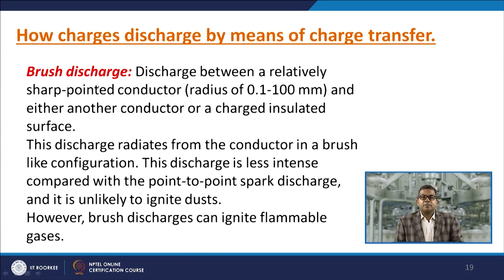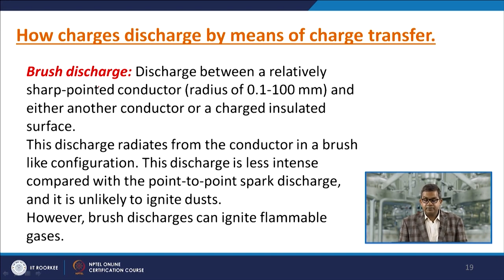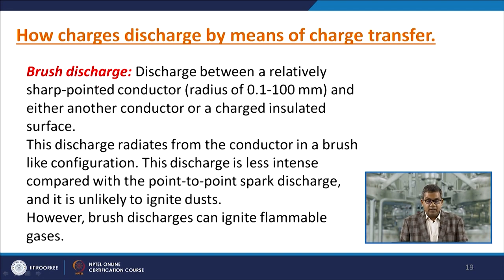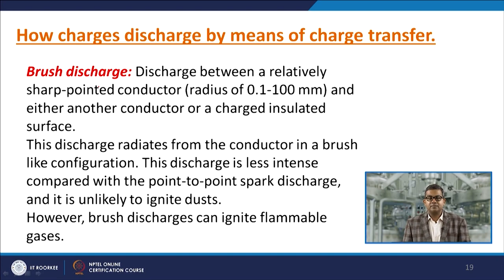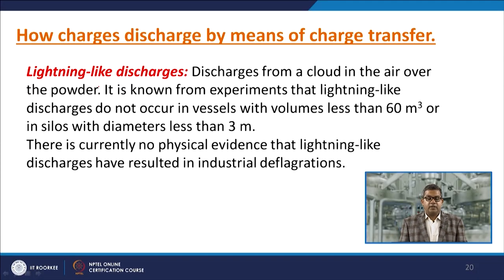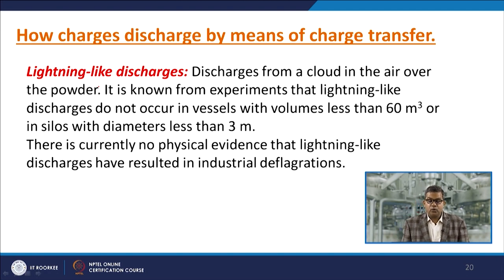Brush discharge occurs between a relatively sharp-pointed conductor — typically with a radius of about 0.1 to 100 millimetres — and either another conductor or a charged insulated surface. The discharge radiates from the conductor in a brush-like configuration. It is less intense than point-to-point spark discharge and is unlikely to ignite dust; however, it can ignite flammable gases. Lightning-like discharges occur from a cloud of powder in air; experiments show they do not occur in vessels with volume less than 60 cubic metres or silos with diameter less than 3 metres, and there is currently no physical evidence of lightning-like discharges causing industrial deflagration.